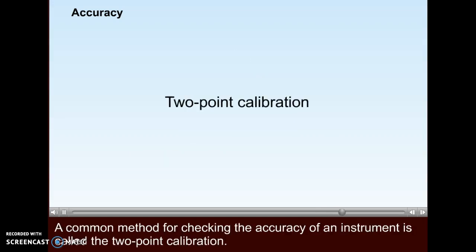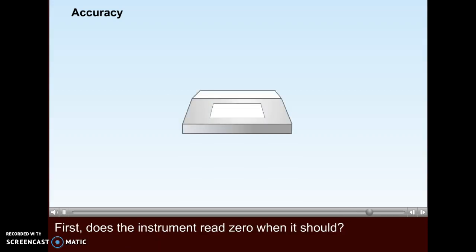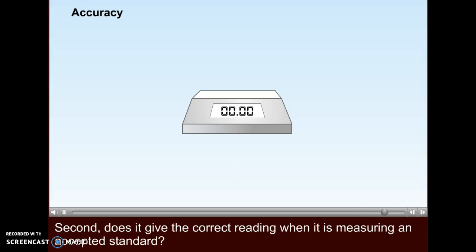A common method for checking the accuracy of an instrument is called the two-point calibration. First, does the instrument read zero when it should? Second, does it give the correct reading when it is measuring an accepted standard?